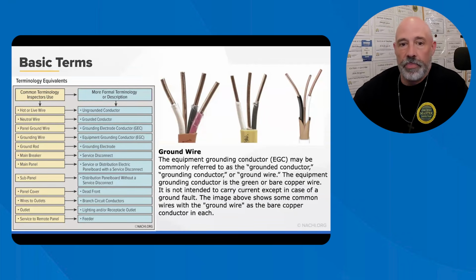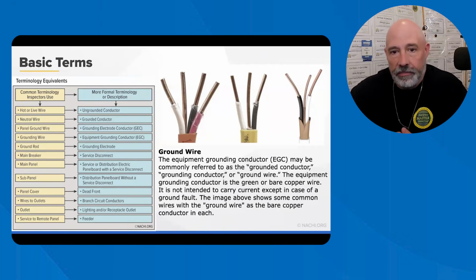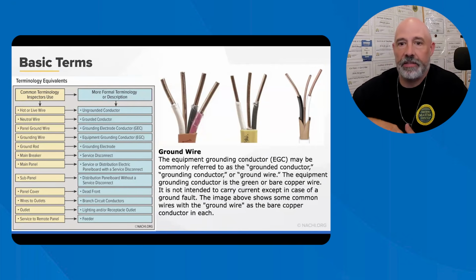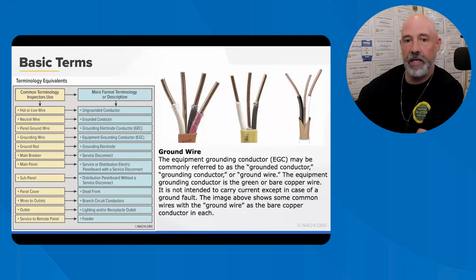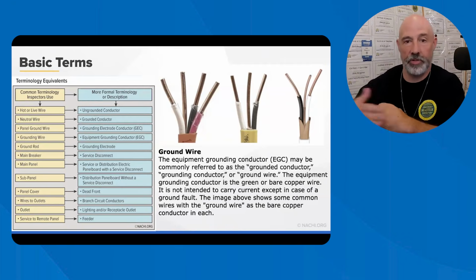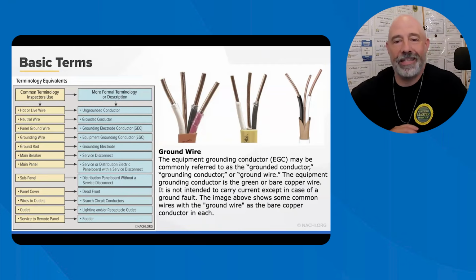So you got kcmil, which is the conductor size designation used for conductors larger than 4 gauge wire. You got the hot conductor, which is the ungrounded current carrying conductor, typically black or red. You got the GFCI, which is the ground fault circuit interrupter. You have the line, that is the incoming side of the electrical equipment. So if you're looking at a GFCI, a lot of them will have line in, that's what it's talking about, and then it'll have load on the other side. And the load is the outgoing side. So that way you can daisy chain later on, and we'll get into that a little bit later on in this course too.